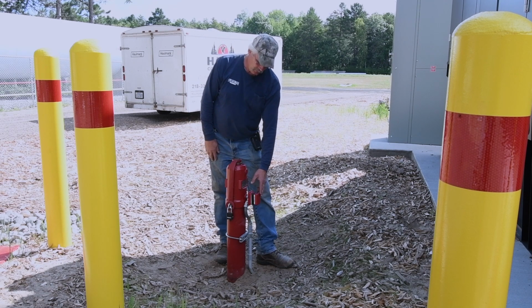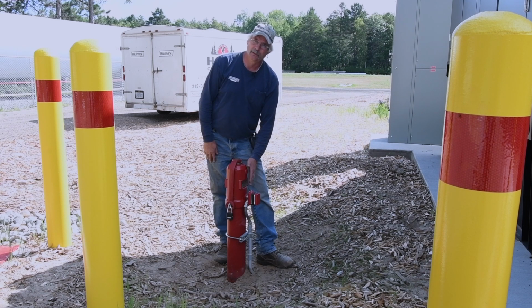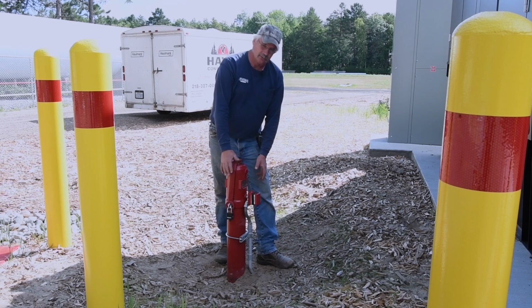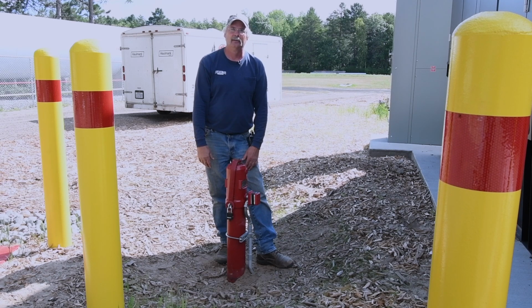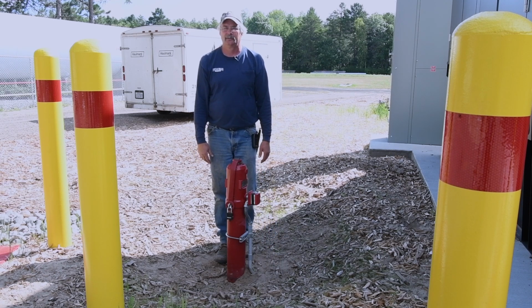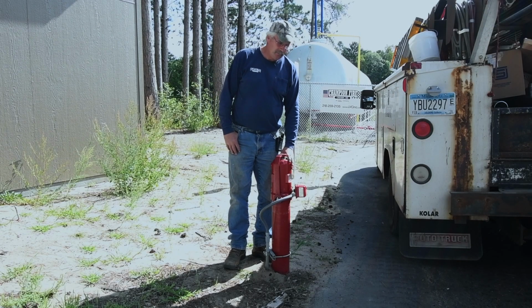So it's always important to check these things once a year and certify and test them, and that's the reason for it, is to make sure this valve is completely open and the sight glass is working, the controls are working, the handle's here in case of emergency. That'll do it. Okay, here we have another PIV.